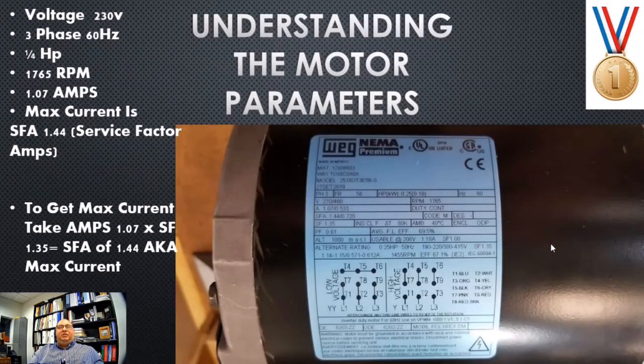So let's understand what we're looking for in the motor parameters. This was step one. If we look at the motor nameplate here, we see that it's a 3-phase motor. We also see that it's 1/4 horsepower, 0.25 HP. Some VFD drives, like the Westinghouse, you have to set up for kW, which is not a big deal because the kW is there if we need it. It's 0.18 kW, but most drives use horsepower. We also need to know the RPMs, 1765, which is important because the drive needs to know how fast it needs to rotate the shaft in the motor.